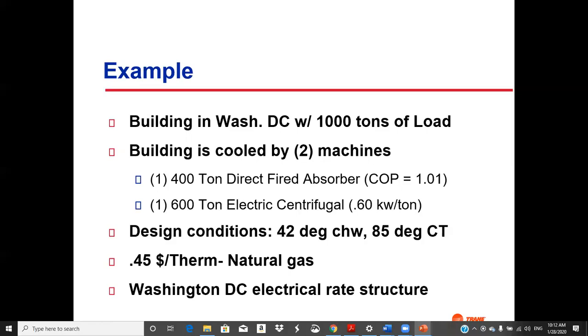Tech, I think, runs 42. And by the time it gets to the building, it's piped underground and pumped and all that stuff and comes up in Brown Hall. We're probably 44, 45. When it gets to the end of the line, it may be even 45, 46, something like that. So you've got to be a little careful about that. You lose that moisture, that dehumidification capability, before you lose a major part of the sensible cooling.